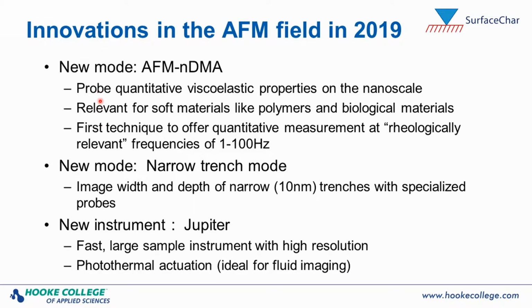The first two are going to be new AFM modes that have come out. The first one is called AFM Nano DMA, and that's to probe nanoscale mechanical properties in the form of viscoelastic properties. It's particularly useful for soft materials like polymers and biological materials that are viscoelastic, meaning that their mechanical properties are dependent on the frequency at which they're measured. And this is really the first technique to offer an accurate and quantitative measurement at what we refer to as rheologically relevant frequencies, which is a low frequency domain of 1 to 100 hertz.